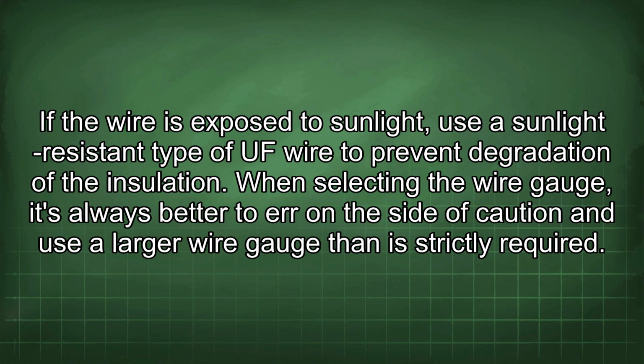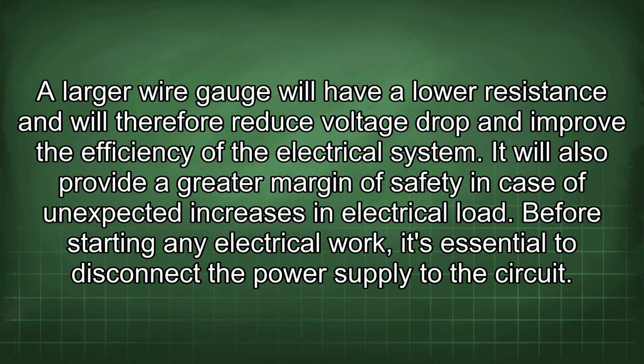When selecting the wire gauge, it's always better to err on the side of caution and use a larger wire gauge than is strictly required. A larger wire gauge will have a lower resistance and will therefore reduce voltage drop and improve the efficiency of the electrical system. It will also provide a greater margin of safety in case of unexpected increases in electrical load.